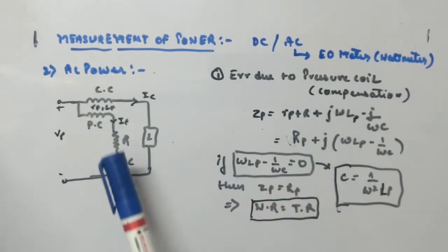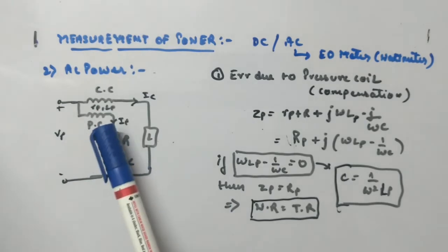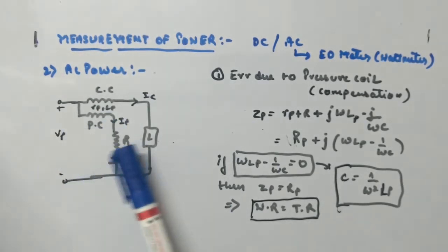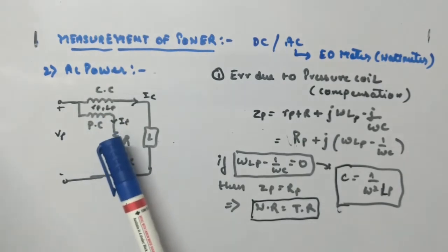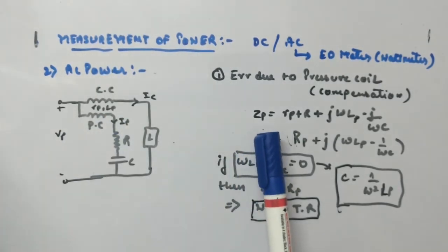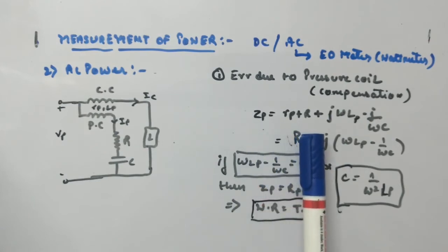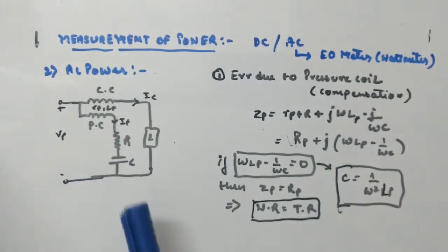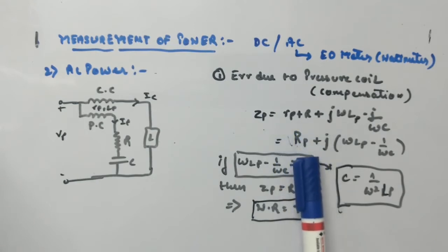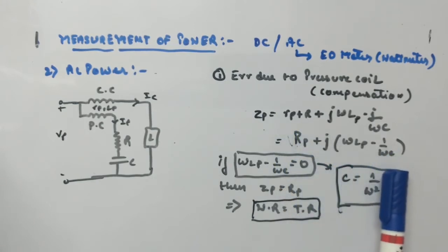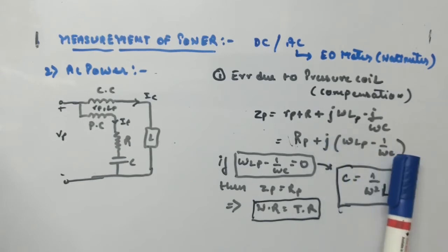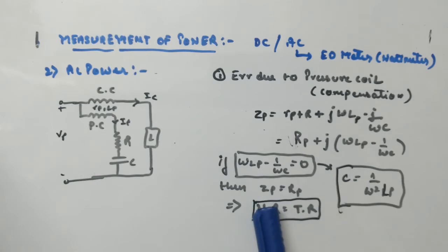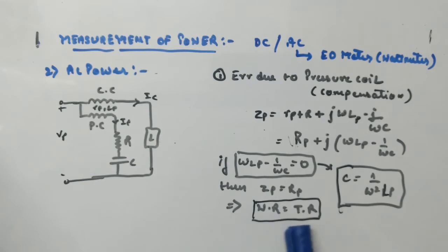Whatever the value of L will be, C will be chosen in such a way that it nullifies the effect of the inductor, and the total impedance of the pressure coil branch becomes purely resistive. So Zp equals rp plus capital R plus jωLp minus j/(ωC). This is the total impedance. If we keep the reactive term zero, the impedance becomes purely resistive, which means the wattmeter reading equals the true reading with no error.